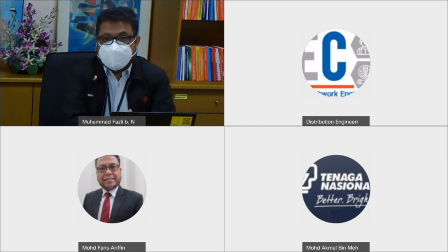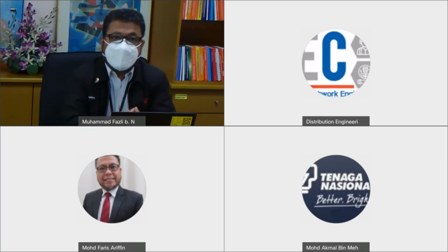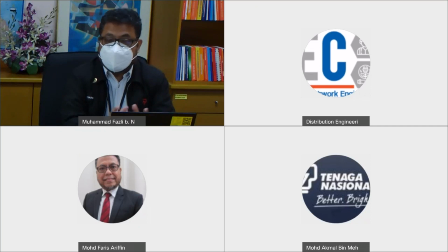And we have to also install line surge arresters. For 33 kV, we recommend that you use distribution class 2, or now we call it a station class, because of the high energy absorption level. It can absorb more energy from the lightning current, and it can dissipate or discharge the lightning current to ground. Because we are finding that there are also multiple strikes on the same line.